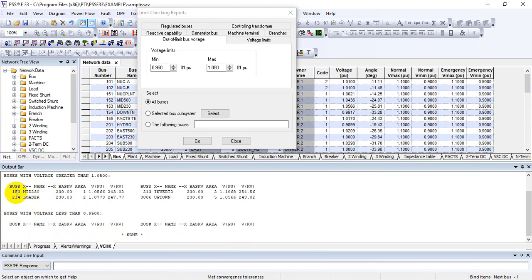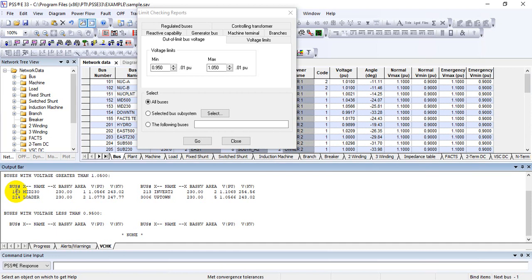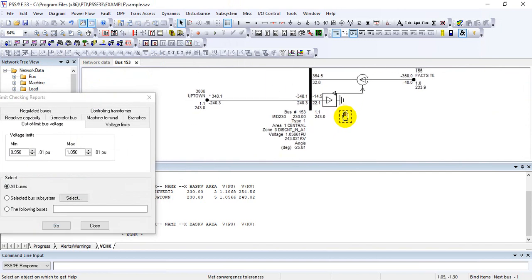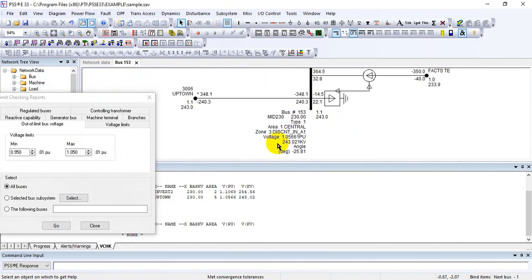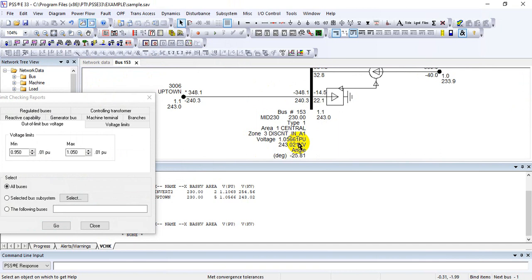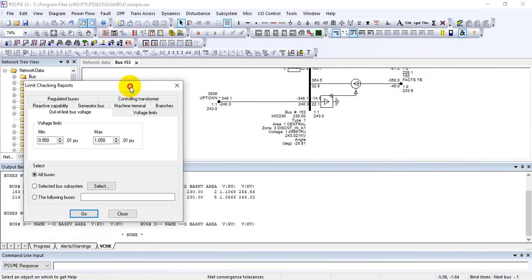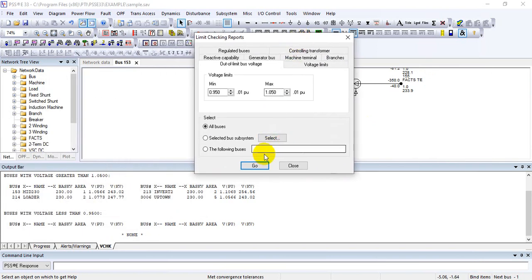When there is an over-voltage problem, you can view the voltage at each bus individually by double-clicking on the bus number — a graphic display will open. Here you can see a STATCOM is available and most of the reactive power is there, giving a voltage of 1.05661. In order to mitigate this you can do reactive balancing, which we will see in a later lecture. This is how you can generate the Out-of-Limit Bus Voltage Report.